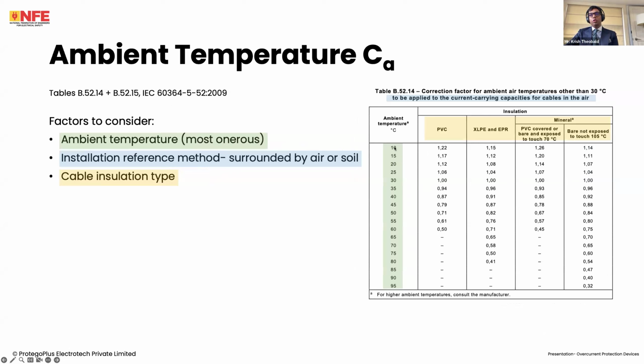Ambient temperature. So what is the ambient temperature? Again, most onerous. So, for example, if you go to some northern parts of India, it can get quite cool during the winters. So maybe it can go to even sub-zero. But during the summers, it can go to maybe 40. So, just because 10 or 0 is the more favorable value doesn't mean you can take it. Because of the most onerous case, the cable should be carrying the same amount of load in the hotter climate. So, I would choose the most onerous value.